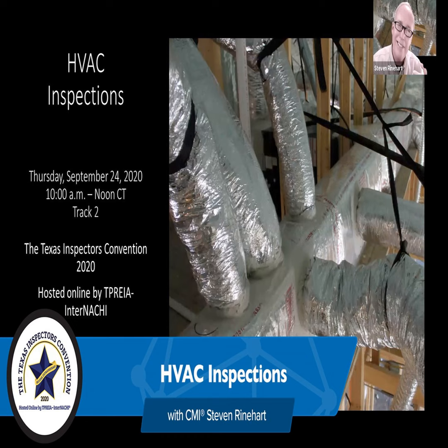So I want to follow that flue all the way up. I want to see it not touch anything combustible that goes through the ceiling. I want to see flashing at the ceiling. When I go into the attic, I don't want to see it buried in insulation. I don't want to see flex duct wrapped around the flue trying to get to some other direction.